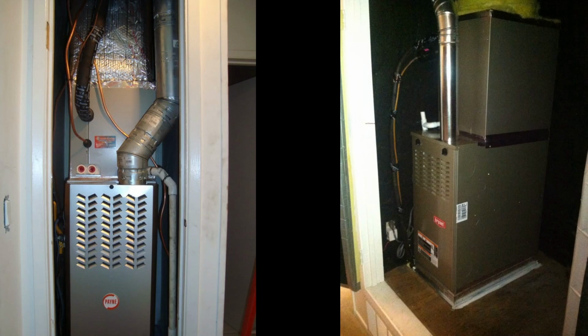Over on the right hand side, you'll see another one. And remember, I was talking about a filter base. If you look down below at the far bottom on the base of that closet, you will see a 1-inch filter base. The white material that you see that looks like it's painted is called mastic. It's a duct sealant. So what a lot of people do is they'll drill that in, and then we will put duct sealant around, all the way around, to keep air from coming into the return air from other sources besides the return air. If you look at the far left bottom of that picture, you will see the return air grill at the bottom.